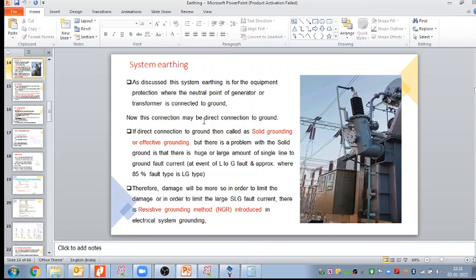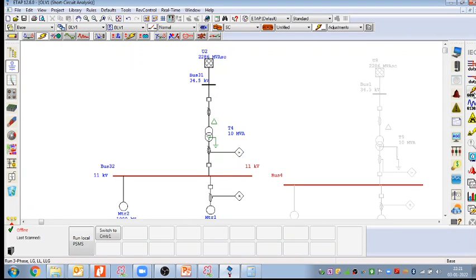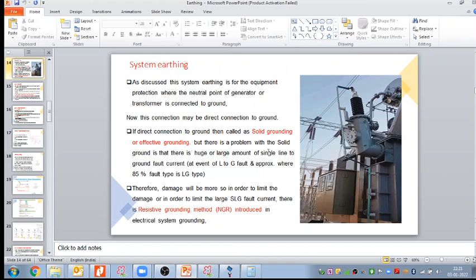So system earthing may be a direct connection to the ground, and if it is a direct connection, it is called solid grounding or effective grounding. But the problem with solid grounding is that there is a huge or large single line to ground fault current. As we can see here, at the time of the fault, let me take this example: the fault is line to ground, and 7.26 kilo ampere current is flowing. So the disadvantage of this kind of grounding is that a large amount of single line to ground fault current flows in the event of a line to ground fault, and approximately 85% of fault types are line to ground faults. So a huge amount of current is flowing, and therefore the damage will be more because the fault current is more.